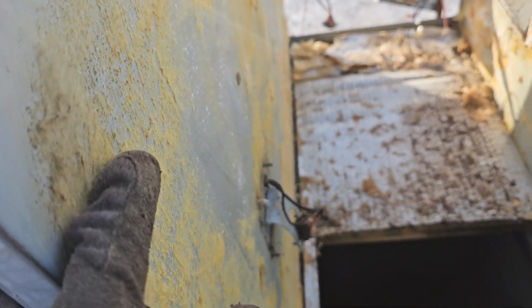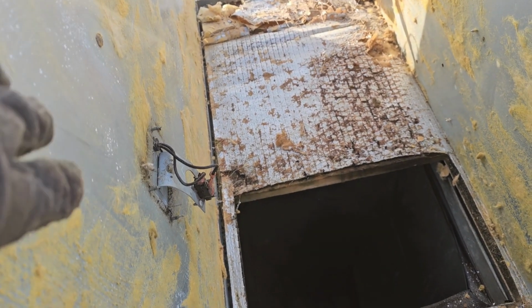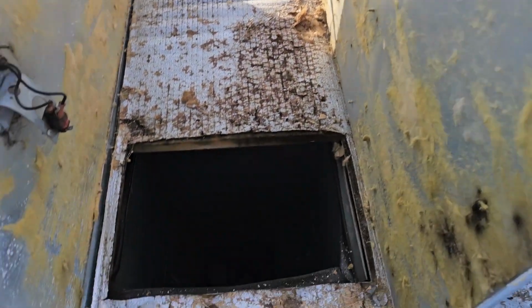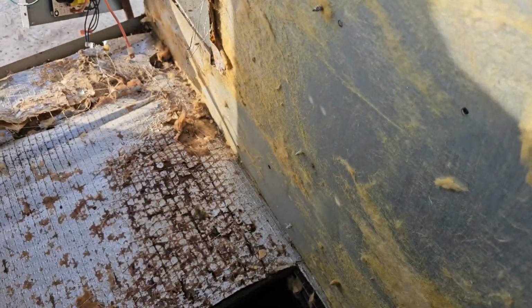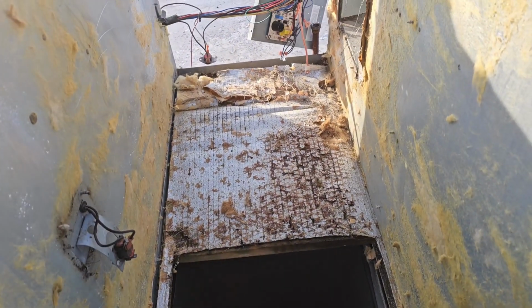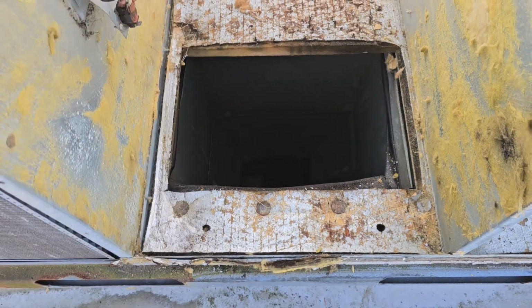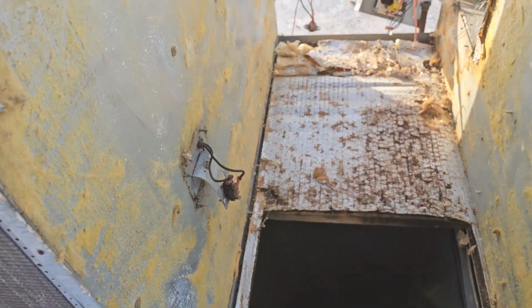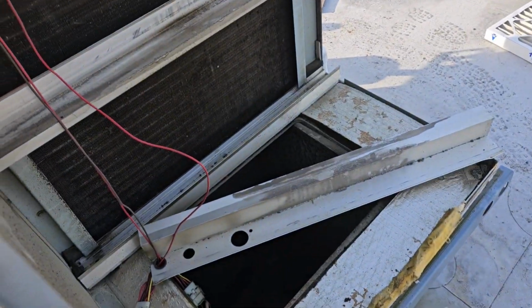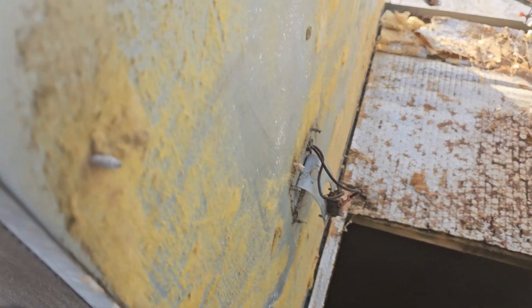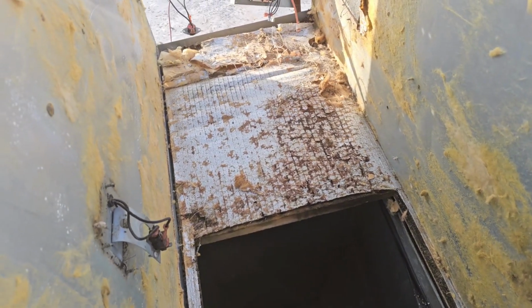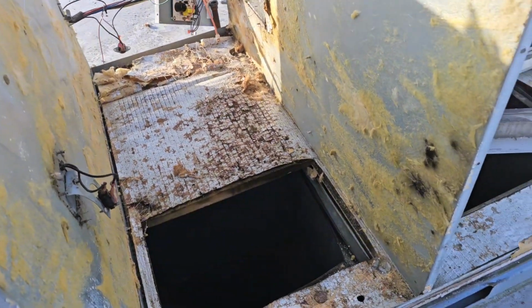Because this insulation on the side, I didn't have any sheet metal to wedge in between the heat exchanger and the insulation, so I didn't rip all the insulation taking it out. This insulation was in really rough shape, just really brittle, so I just ripped it all off. Yeah, I was able to keep the insulation on the bottom, but it's not going to get insulation, unfortunately, which is fine. The only place you're gonna get transfer of heat is this side here. So, well, it's an old unit, so if it runs two minutes longer every cycle, what are you gonna do?